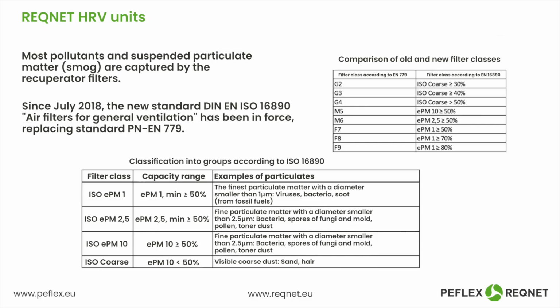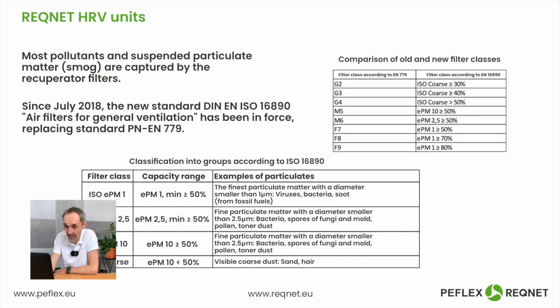Because in other solutions, or very often, clients ask whether they can cut filters themselves or use filters made from G4 filter fabric. But where, in reality, are these filters? These G4 filters only catch the coarsest fractions of pollutants, like sand, hair, or as I like to joke, flies and mosquitoes. But in reality, filtration should start with an M5 class filter, that is, the ePM10 filter, which captures 50% of PM10 dust particles.